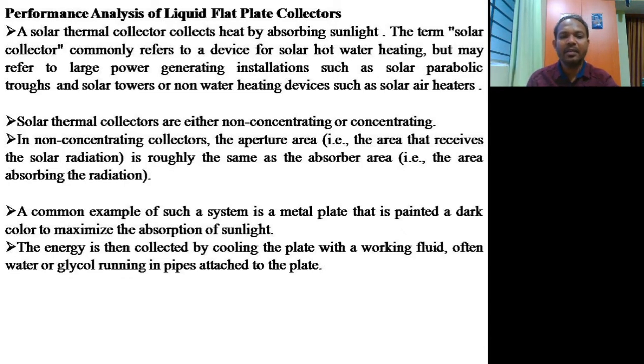The absorber plate is usually made of thin metal sheet ranging in thickness from 0.2 to 0.7 mm, while the tubes, which are also made of metal, preferably aluminum or copper because of their higher thermal conductivity, range in diameter from 1 to 1.5 centimeters. They are soldered, brazed, and pressure bonded to the bottom of the absorber plate with a pitch ranging from 5 to 12 centimeters.